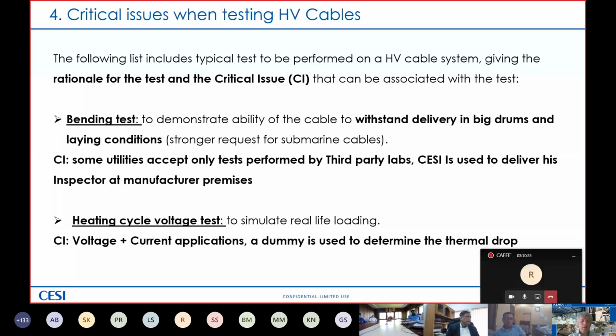For example, bending test. The bending test is the first test to be performed. This is performed to demonstrate the ability of the cable to withstand delivery in big drums and also to withstand the laying condition. And this is a stronger request for submarine cables. There are even tensile tests much more severe than this bending test. The critical issue is that some utilities accept only tests performed by third-party laboratories. We are used, vice versa, to deliver our inspector to the manufacturer premises. But in case, we can rent tools locally and perform it in our laboratory.